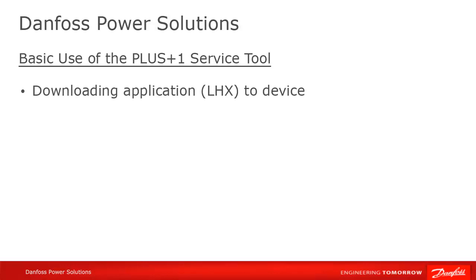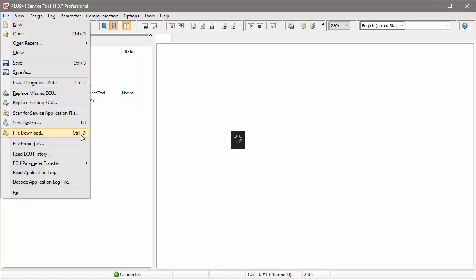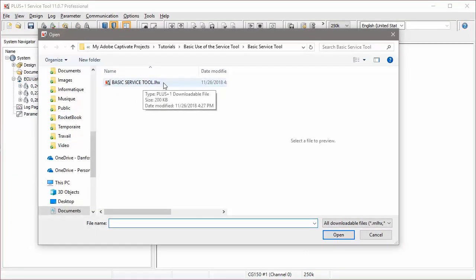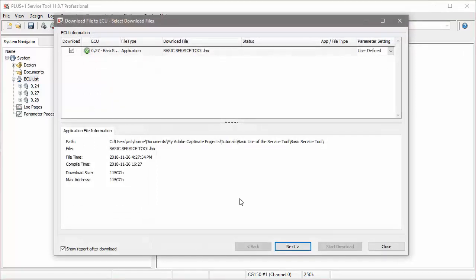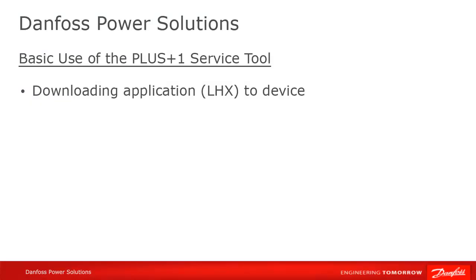One of the essential functions of the service tool is to download applications to the device, be it a controller, a display, or any other Plus One programmable ECU. You can do this by selecting File Download from the File menu, or by typing Ctrl+D, and then selecting the application. Application files normally have an LHX file extension. You can also double-click on an LHX file directly in Windows Explorer, which will open the service tool and initiate a download.